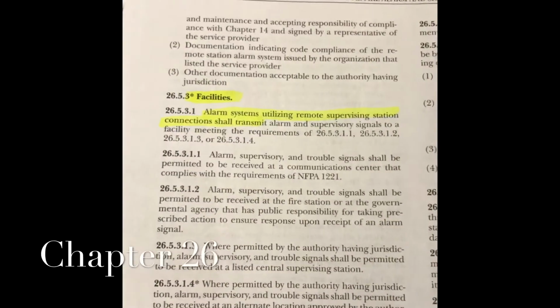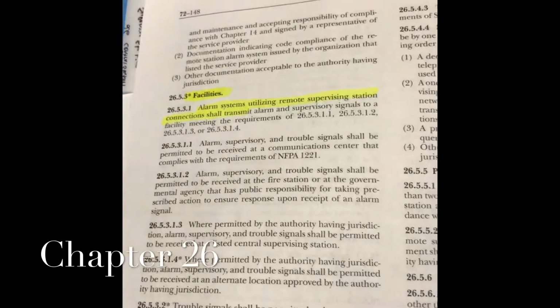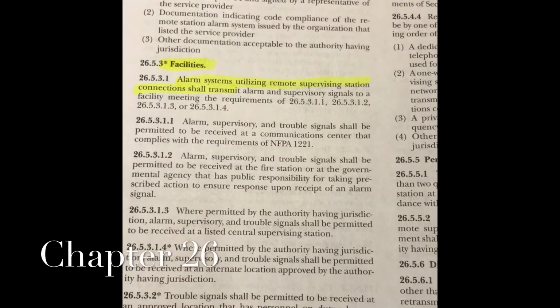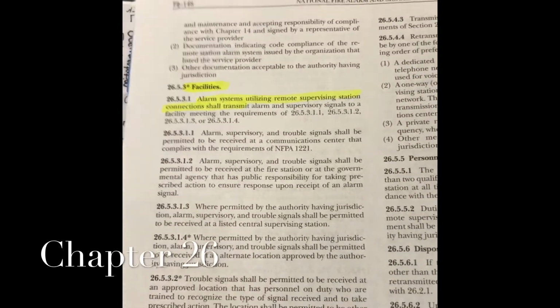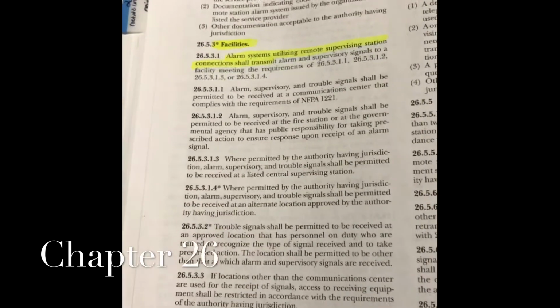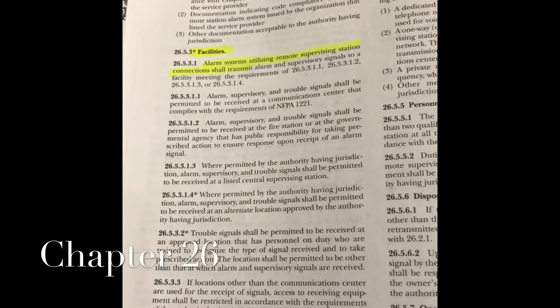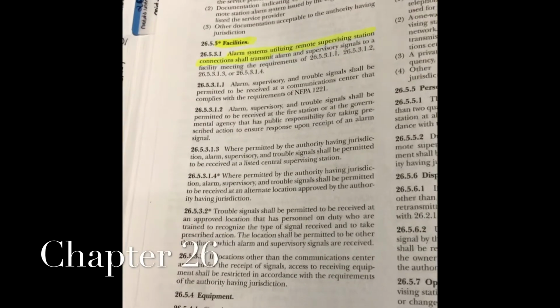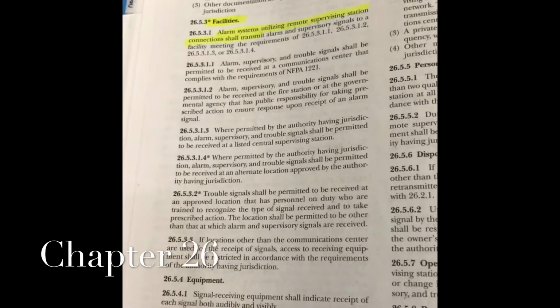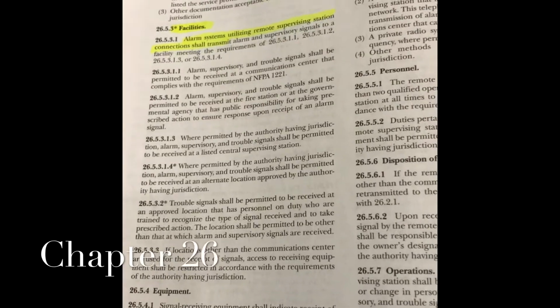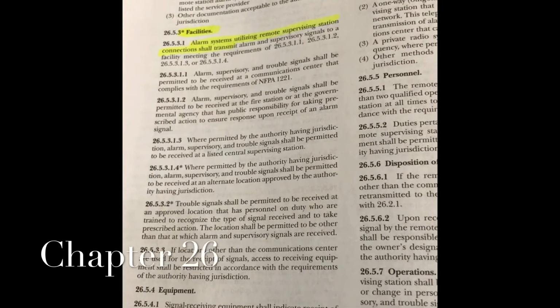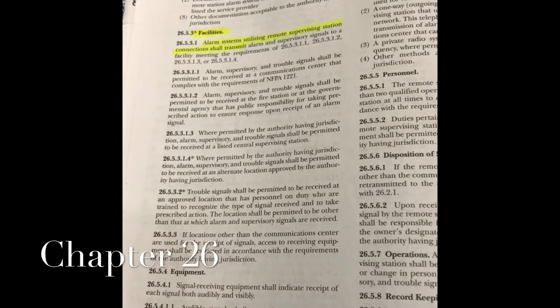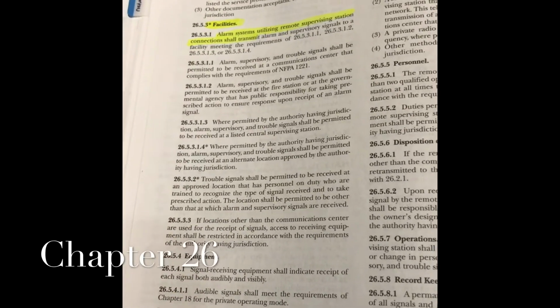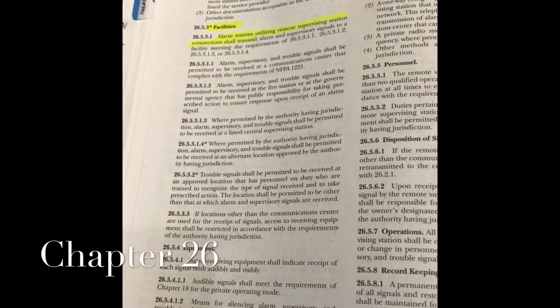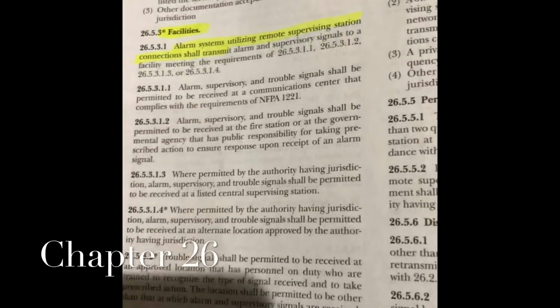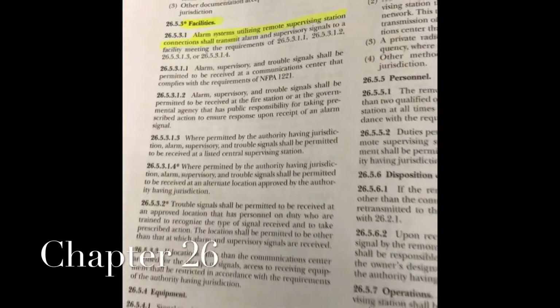Right here in 26.5.3.1, this is dealing with remote supervisory stations, and that's basically the same thing as a central station. Besides, with central stations, they go through a lot more strict requirements. A remote station is basically a communication center that receives the signals from your fire alarm company that does the monitoring, and you pay a monthly monitoring fee for it, and usually that's how it goes. 26.5.3.1 deals with remote stations.